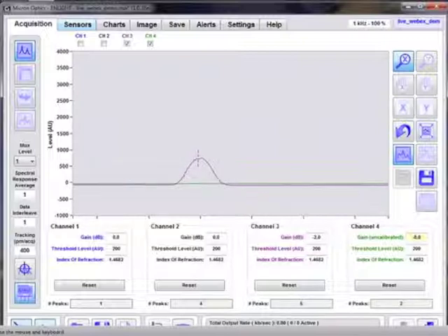you were mentioning, Dan? Which issues? Bogging down the system computationally. Memory allocation. I think there's a maximum number of averages on the SM130. In the case of the SM130, FBG averaging is actually done inside the interrogator itself, which I believe has a maximum number of averages of 10,000. So if you're acquiring at 1 kilohertz, that's going to give you a 10-second roving window of the average.